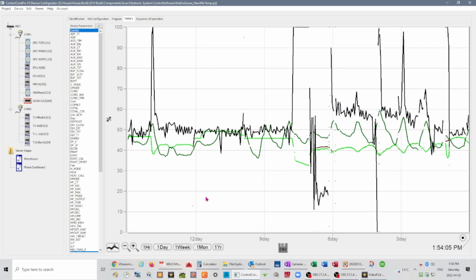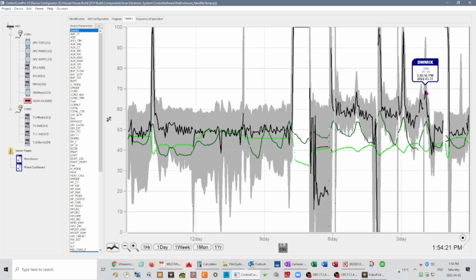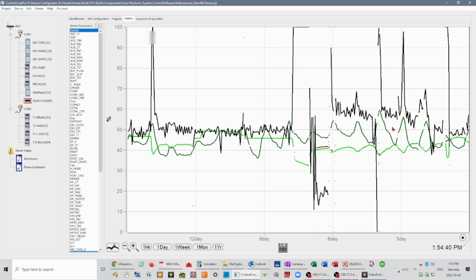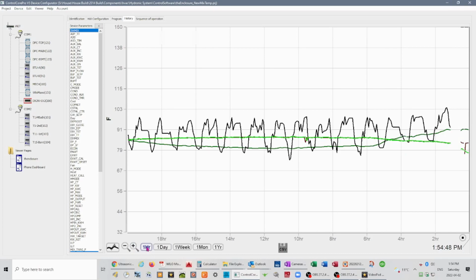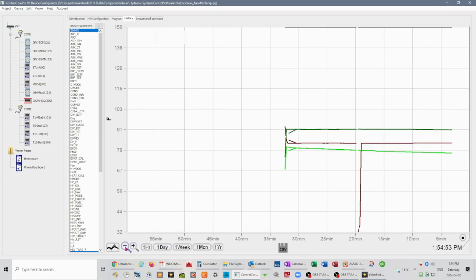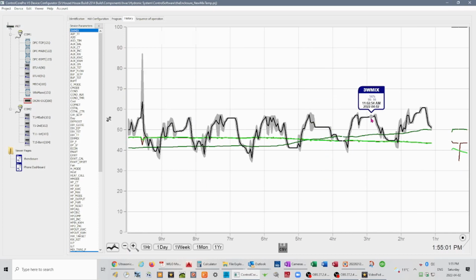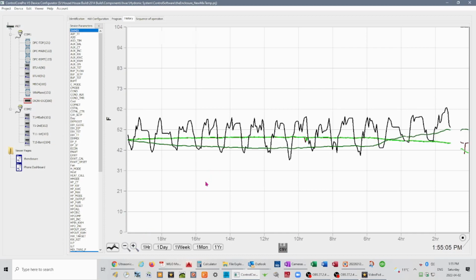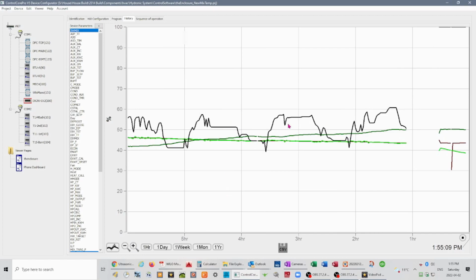And if we add in the three-way mixer, you can actually see that the degree, the percentage that it's closed and open, has completely changed in magnitude. Basically it was maxing out at kind of 40 to 60%. Now it's doing 60, and it even goes up to 100%, where it knows it doesn't need anything from the buffer tank. So you can see a lot more magnitude to the mixing valve's movements here. And if we look at that on a very close scale, you can also see that there are a lot of flat areas in the mixing valve, meaning that it isn't cycling way above or below its requirement. It is responding in increments to the requirement so that it can move as little as possible to meet the required temperature. So it's as efficient as possible.